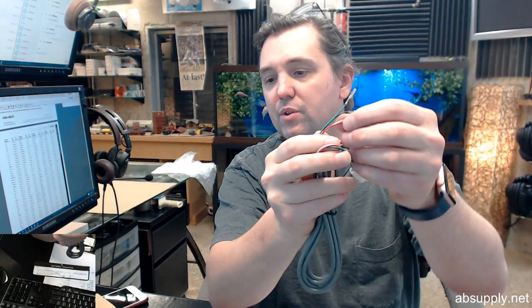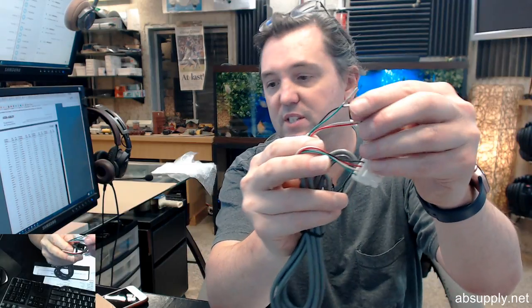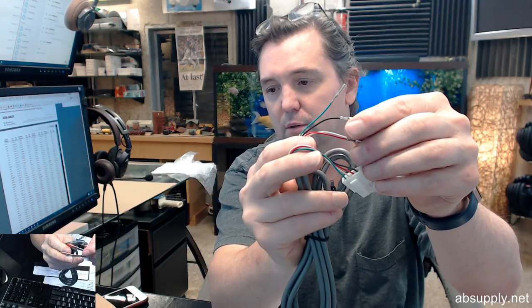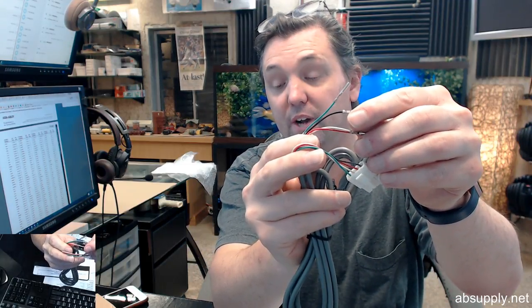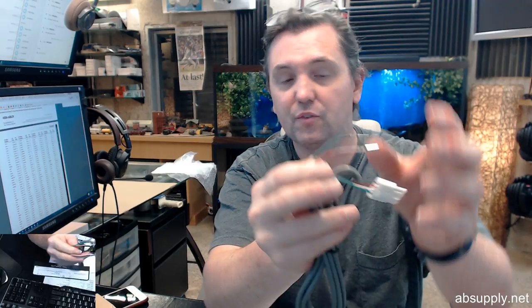On a microprocessor U series control or other suitable power source, whatever is feeding the power. Then, of course, your white and green are going to go down to the activation or presence sensor input on the door control. Turn on the power and wait a minimum of 10 seconds for the sensor to calibrate.